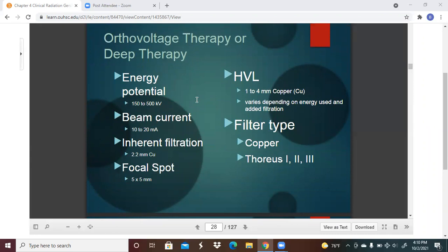Orthovoltage therapy, or deep therapy. So we're looking at an energy potential of 150 to 500 kV. The beam current is going to be 10 to 20 milliamps. The inherent filtration here is 2.2 millimeters of copper. Focal spot is going to be 5 by 5. Half value layer is 1 to 4 millimeters of copper, but it varies depending on the energy used and the added filtration. And there you can see the different filter types.